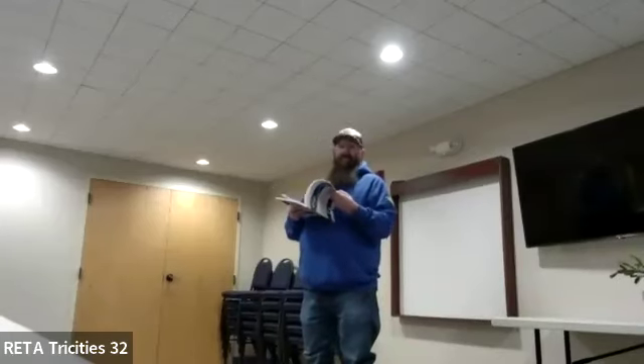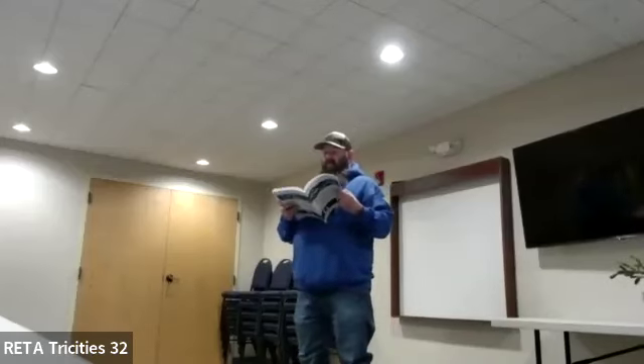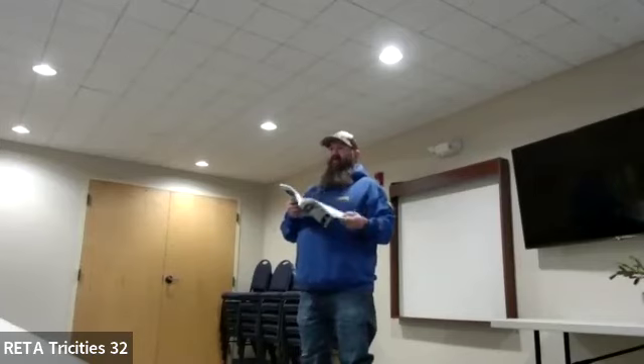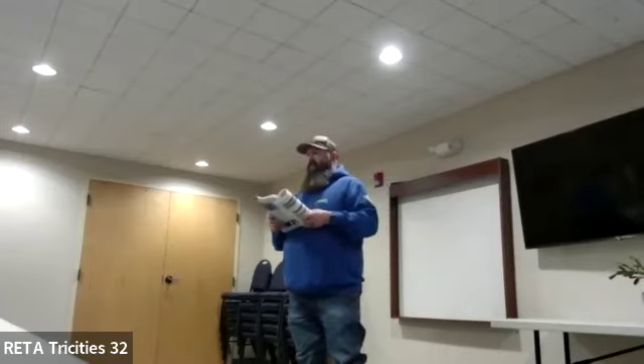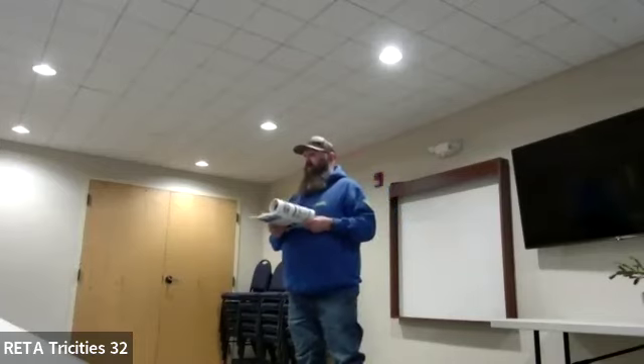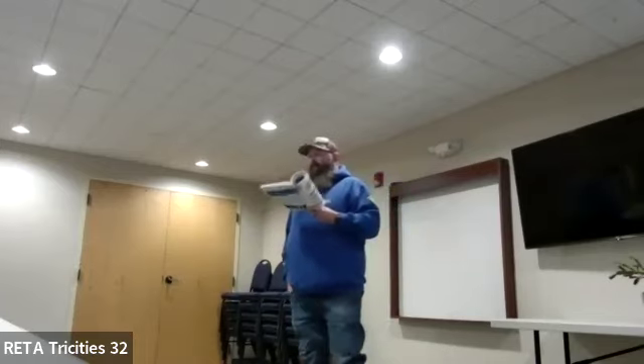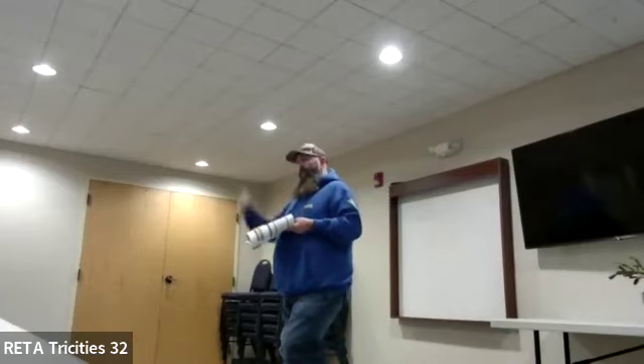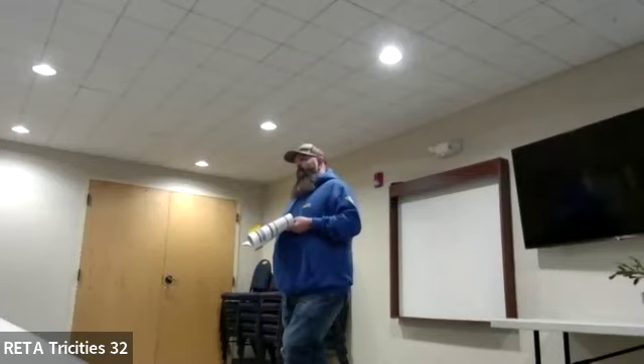I'm more pointing out the unique ones, the ones that we wouldn't think of, and one would be a secondary coolant. The other one, my favorite one, is how many of you do monthlies and weeklies on your eye washes and meet the new criteria? They've got a whole set of PMs we all need to be doing. Some of them your safety person would probably cover at the larger facilities, and that's opening the eye wash, pulling the shower, making sure it's fully functioning. Then additional documentation, like your fire reports. Normally you do a fire report every month. You go around and check all your eye washes and everything else.